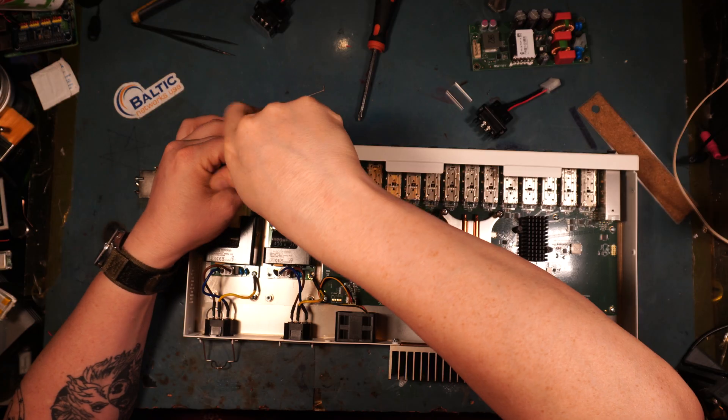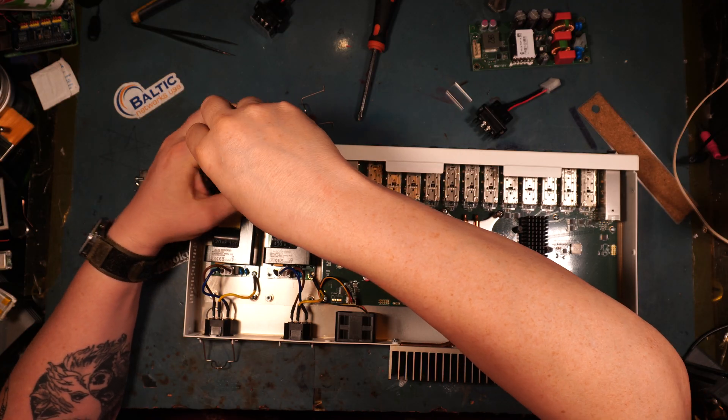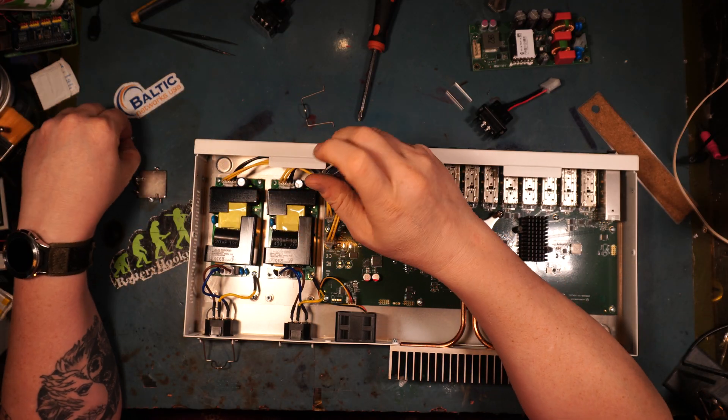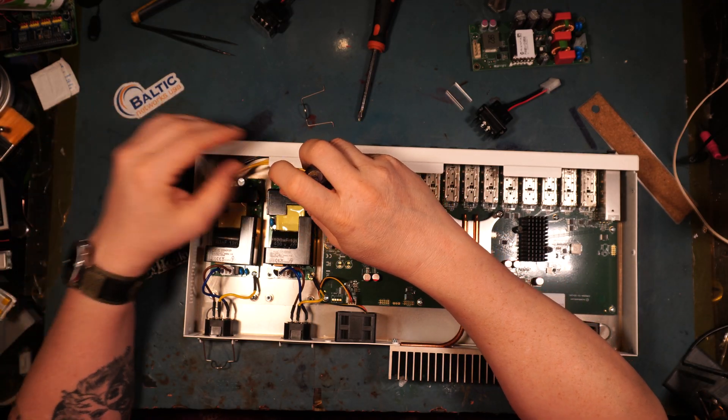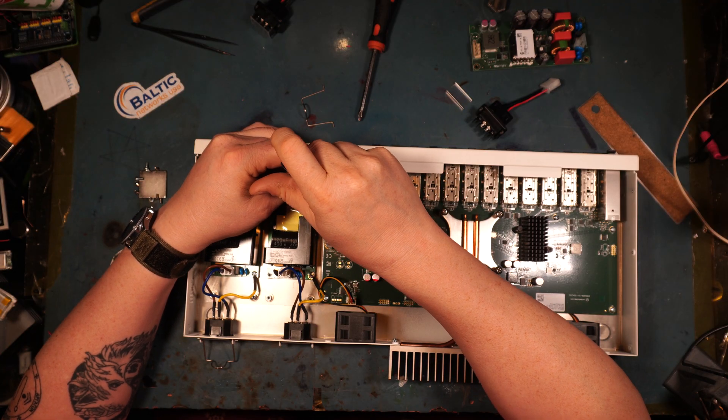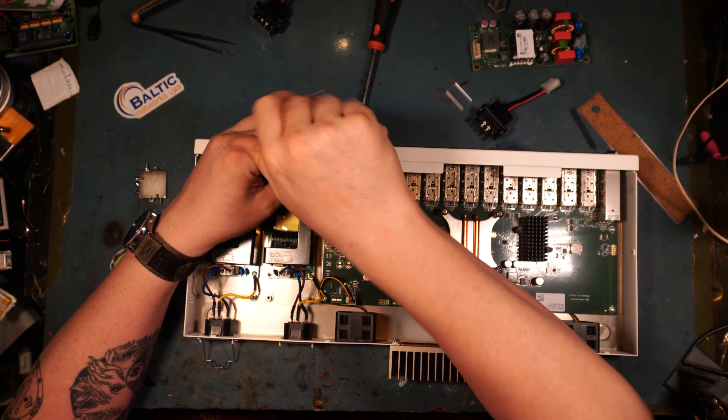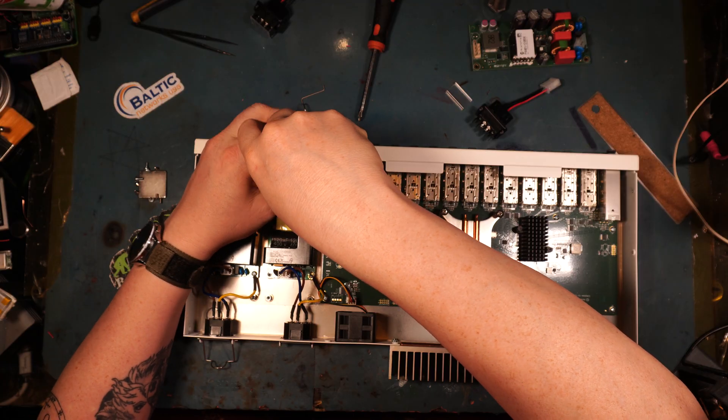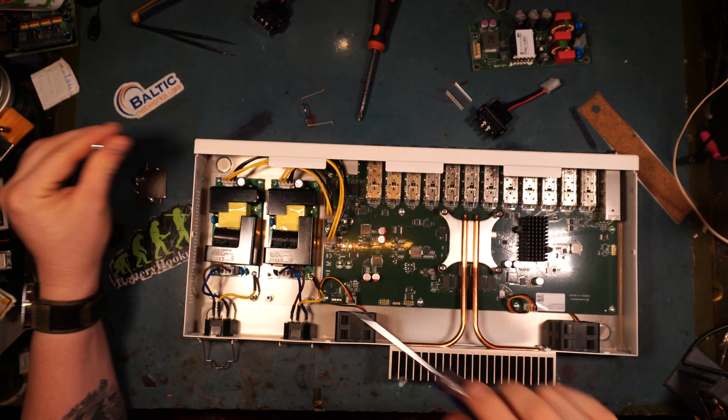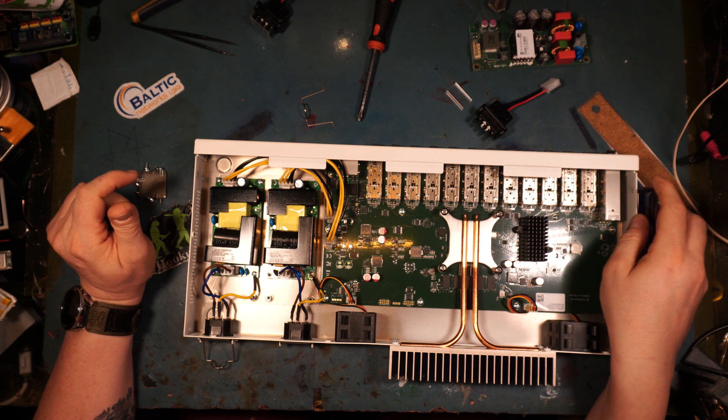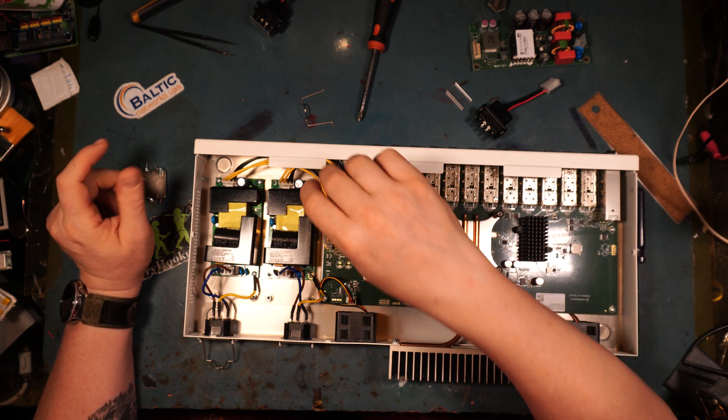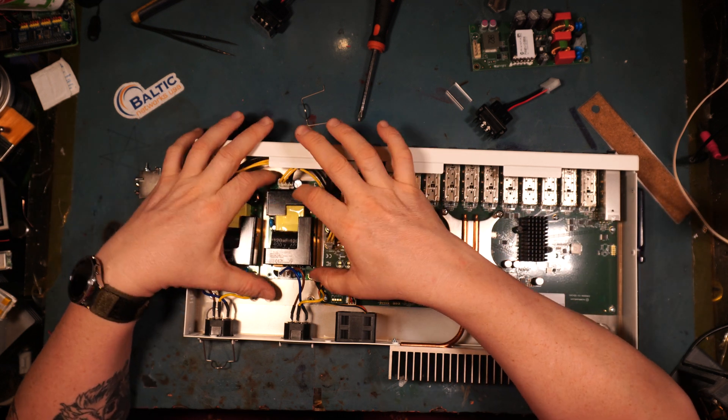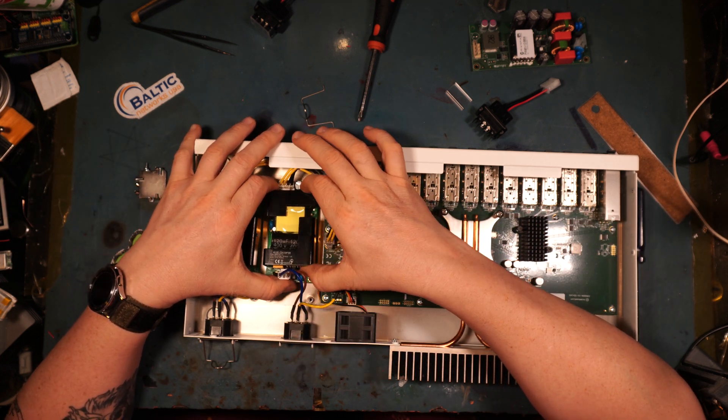Now, I'm going to only swap out one of these power supplies, because honestly, as awesome and great as it would be to have two DC power supplies in this, that would be proper. Have one go to bus A, one go to bus B, right? The client's got small sites, so it's fine to go this route. So I'm not shirking.